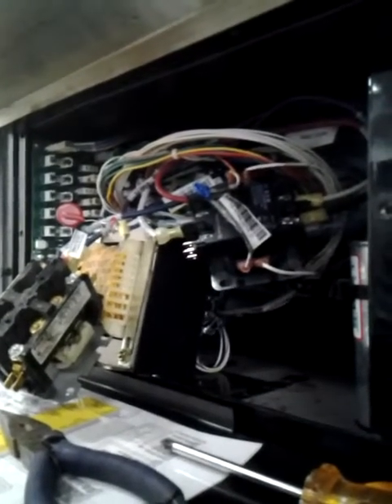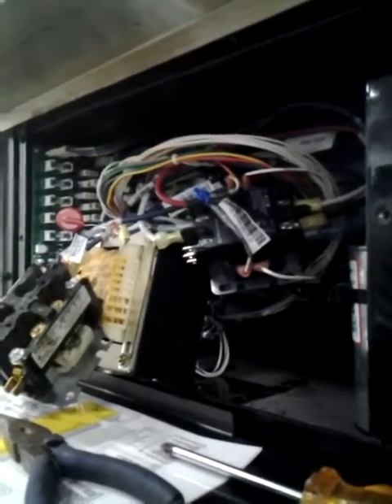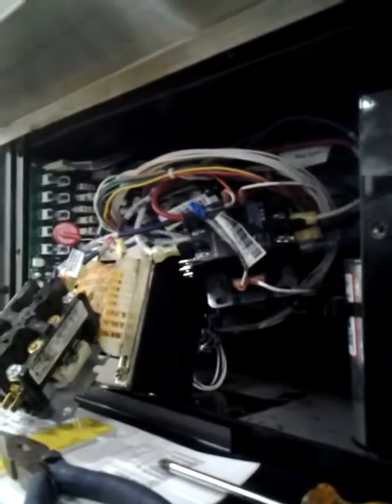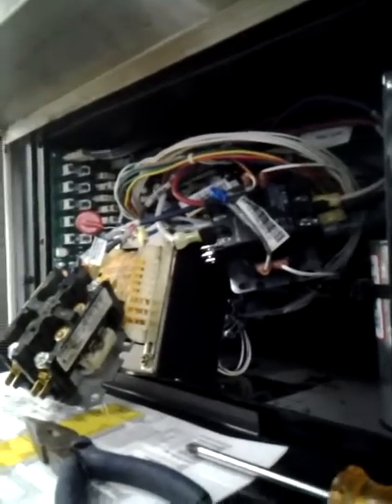What we have here is the electrical compartment of a furnace. Model number is 554. And what it was doing was it was shorting out the breaker. As you can see here, we have a burnout contactor.